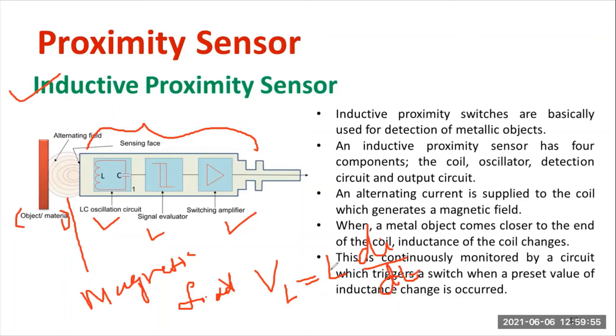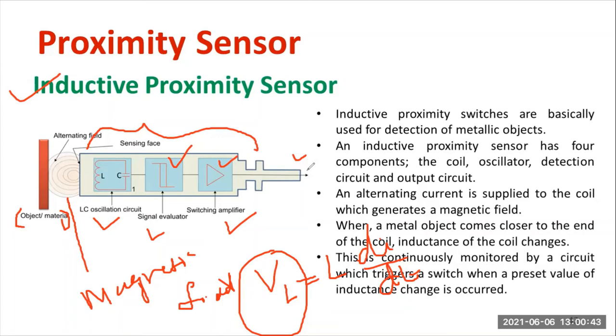As the inductance changes, the voltage also varies. Whenever there are changes in inductance, we know the object is very near to the sensor. The signal is passed through the signal evaluator, which accepts only a suitable band. The output of the signal evaluator is connected to a switching amplifier where the signal gets amplified. According to the nature of the signal, we identify whether the object is nearby or far away. This type is generally called an inductive type proximity sensor and is majorly used for detecting metal objects.